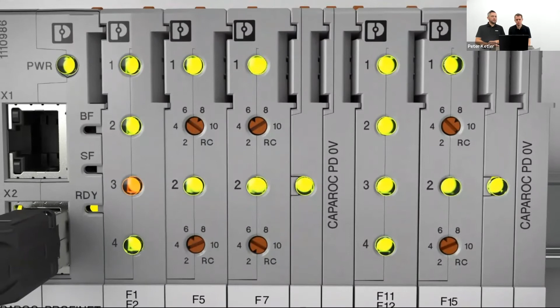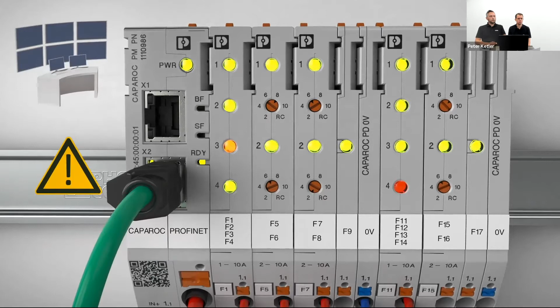Here we can see an overview of the different LEDs. We have green LEDs, which means the channel is switched on and everything is fine, it works. If we have a yellow or orange LED, it will show that maybe something could trip, because it's a pre-warning. That means 80% of the channel is reached, and maybe you have to look at what has happened in the machine. If we have a look at the right yellow LED, we get a failure, it will trip, and we have a red LED to show something is wrong in the machine, and you get information to your PLC via Profinet in that case.